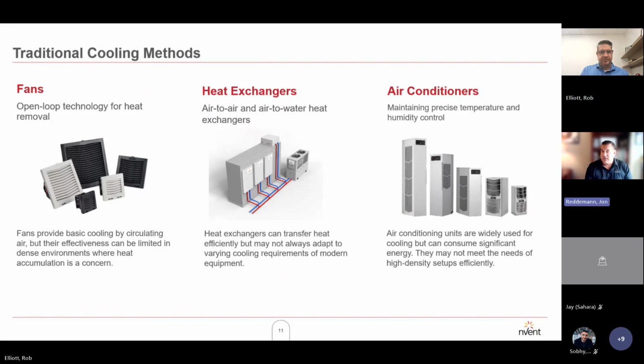So, kind of touched on this. Traditional methods of cooling are fan and filter systems, heat exchangers, air-to-air heat exchangers, and then air conditioning systems. There are air-to-water heat exchangers where we would tap into the process water or a chiller, and that would become an active cooling solution, where we would provide chilled water to a heat exchanger, cycle that through the heat exchanger, and be able to provide cooling for that enclosure.